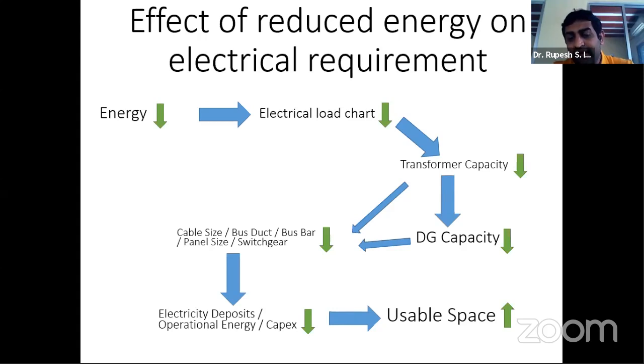And then, very importantly, the electrical deposits that one pays to the ESCOMs or the electricity boards when we take a sanction would come down, because my energy load requirement itself is down. So the deposits would come down, and that way it could lead to an overall capex reduction as well. Of course, the operational energy reduction is guaranteed, and that could lead to an increase in usable space. I could get, let's say, 30 to 40% more usable space on an electrical floor, because all of my energy demand has come down. So this is my collateral in order to develop a zero energy or a highly efficient building.